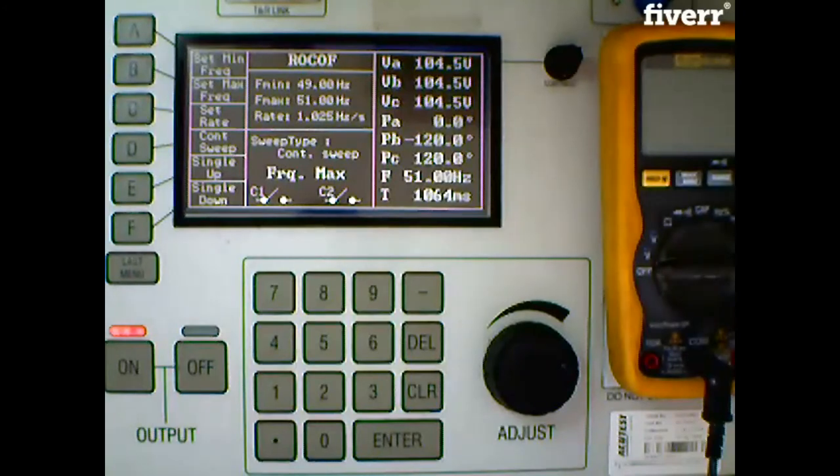Now, that would mean that you would do two things. If you were on your own, you would put at the bottom of the page, you'll see additional comments. You would obviously write in there that you tried all the different filter settings, and the fastest time you could get disconnection was 1064. And you would put that at the bottom of the sheet, and then wait and see what the DNO said to you. If you've got the DNO on site with you, you would have a discussion as to whether he thought the 1064 was going to be acceptable on the higher level. In my opinion, with our little bit of background knowledge I've just been talking about, I think there's not many DNOs that wouldn't let that go.